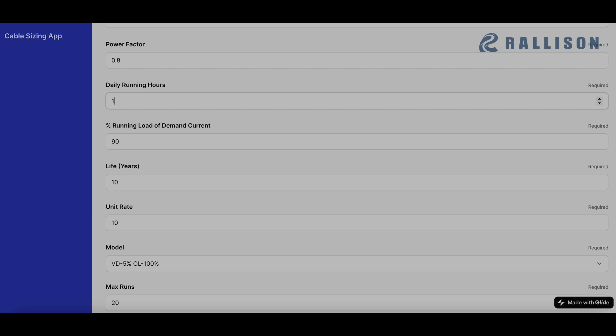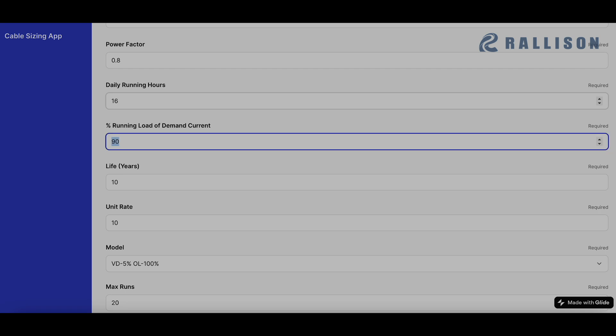These are based on the judgment of the designers that for how many hours daily will the cable be carrying the current that we're designing it for. Say the designer feels that it won't be carrying the current for 24 hours, but it'll be carrying for 16 hours every day for the long period. Then they can simply mention 16 over here.